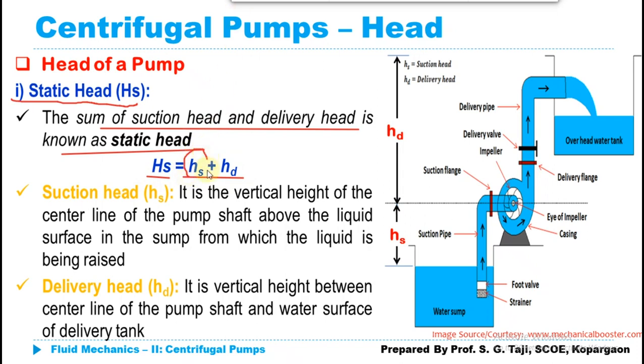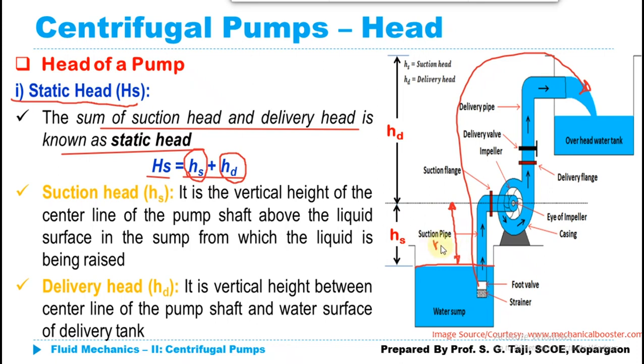Where small hs is the suction head and small hD is the delivery head. If we consider the water level from where we need to take water up to an overhead tank, the head measured from the free surface of liquid to the eye of the impeller is the suction head — where a negative head develops to draw water from the source. The head from the eye of the impeller to the delivery point is the delivery head, hD. Adding these two together gives the static head.